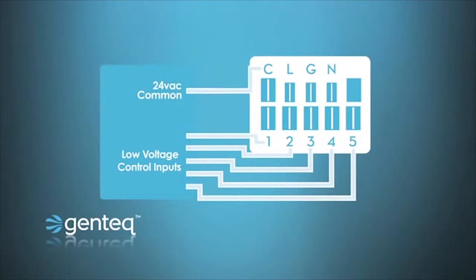Now these taps are also programmed for multi-state inputs, and what that means is you can turn on more than one tap at a time without damaging the motor. In other words, you can energize tap 1 and tap 2 at the same time. The motor will simply do whatever's stored in tap 2. You can turn on 1, 2, and 3, it'll do what's in 3, and so on and so forth.